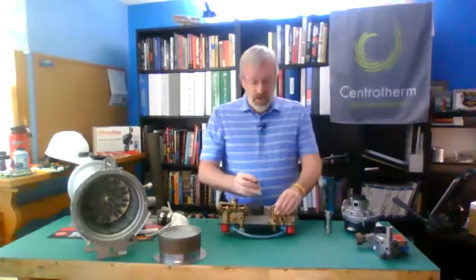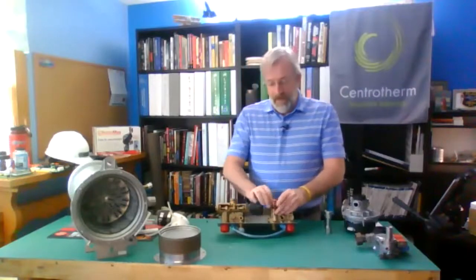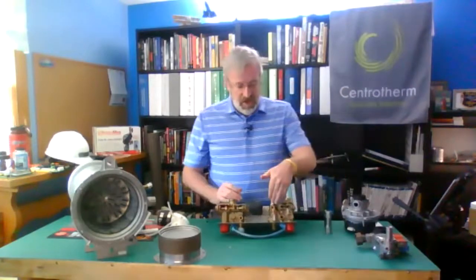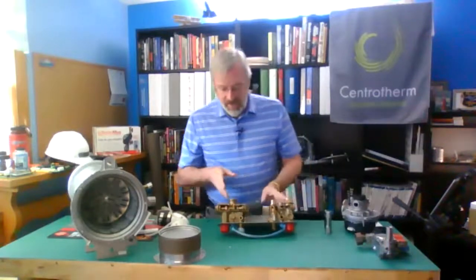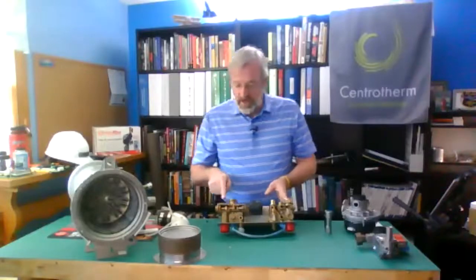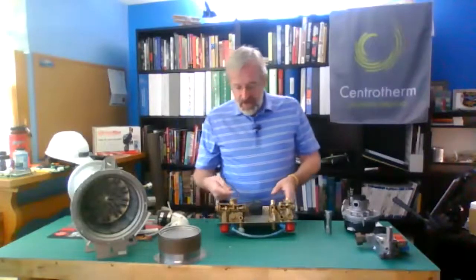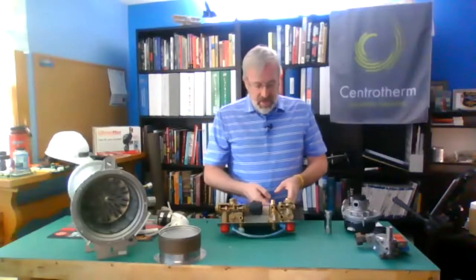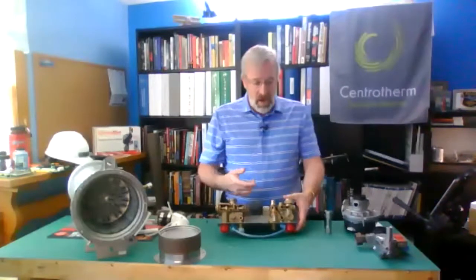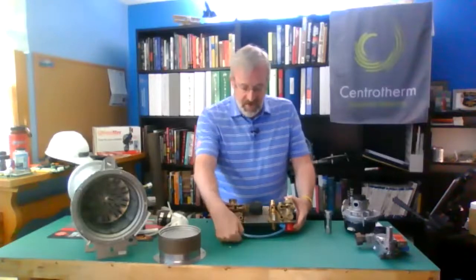So if you take these out and the water's not turned off, you'll get your weekly shower right then and there, save you a little time later. But that's how that's going to work. So this is triggered. When that happens, my diverting valve diverts, and now the flow of the boiler water is no longer headed out here, but it's diverted in through the heat exchanger and back up to the boiler for my boiler water, while my potable water comes in, crosses path across there, picks up the heat energy, and goes down.